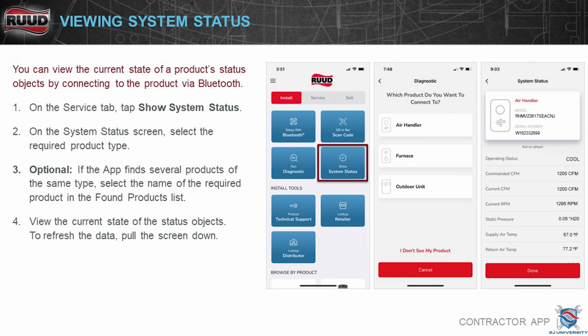So let's jump into the diagnostic side of this a little bit. You can go through your system status, and it'll show you system status. It'll give you the CFMs of your blower, the RPM of the blower. It'll also give you static pressure. Now, the one thing that I will tell you about the static pressure is that it's probably going to be a lot better to use than actually trying to measure static pressure. Okay? The way that they have calculated this is very, very precise, and you're probably going to get a better static pressure out of that than what you're going to actually physically measure. So I just wanted to point that out.